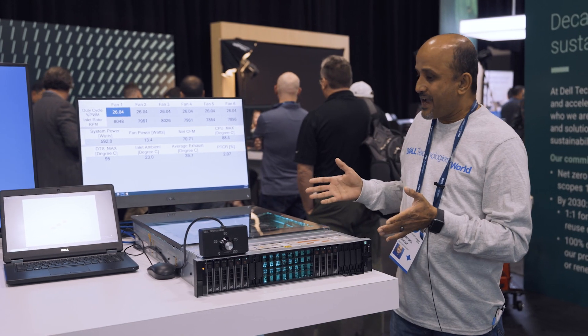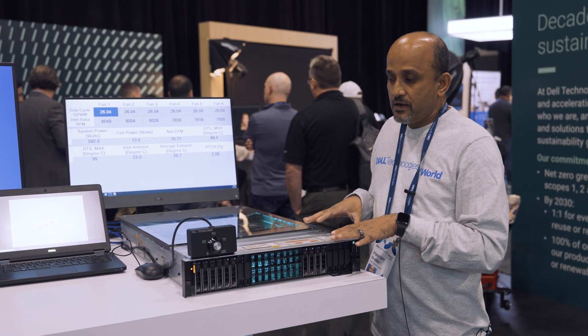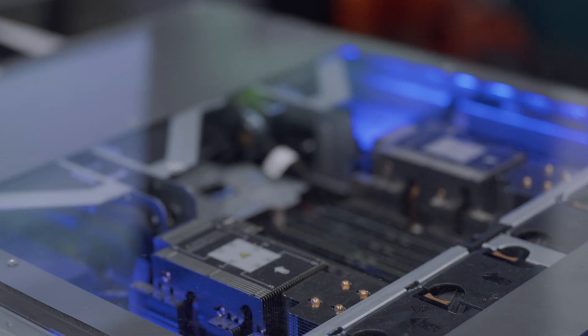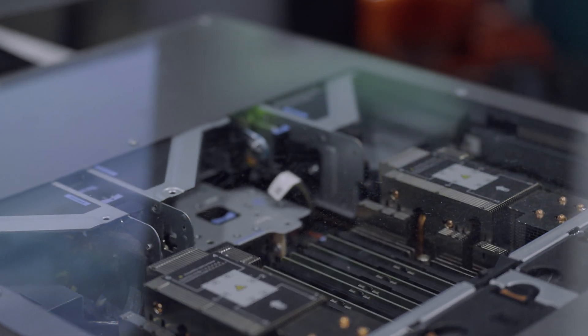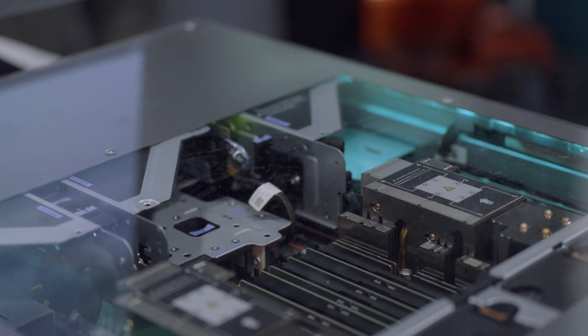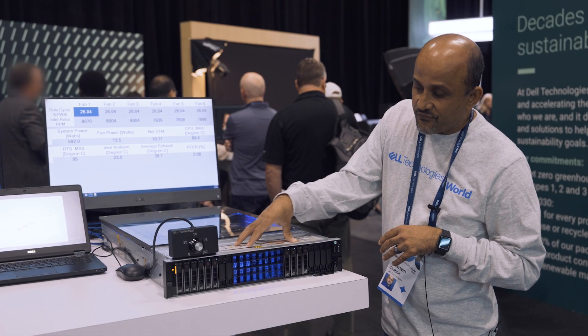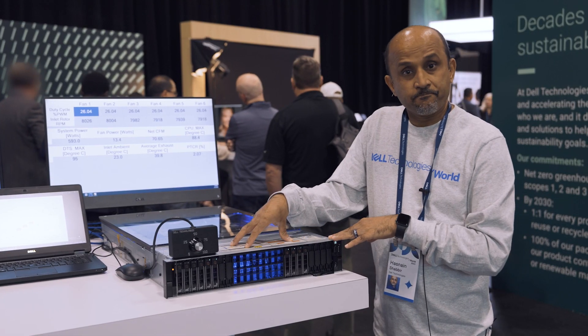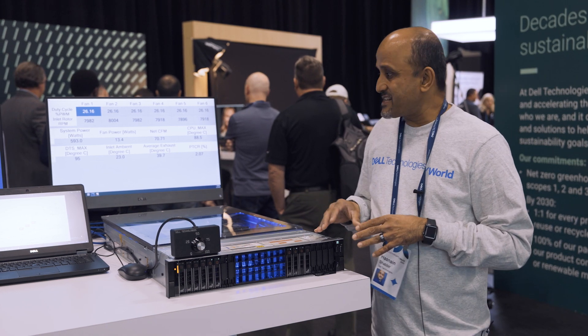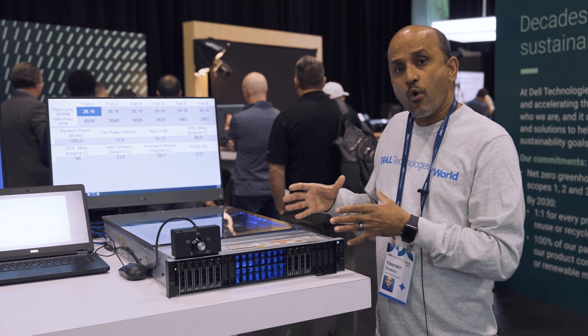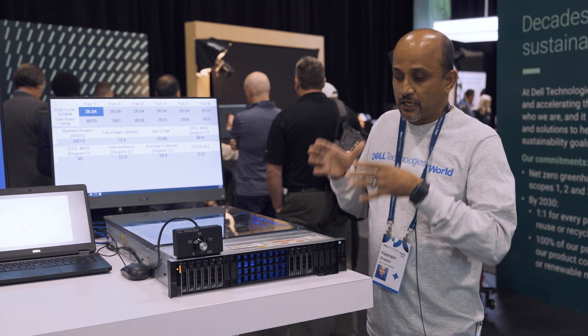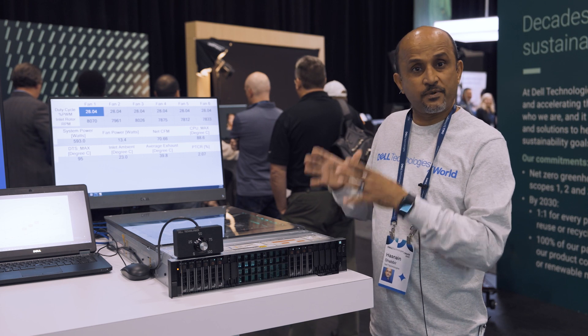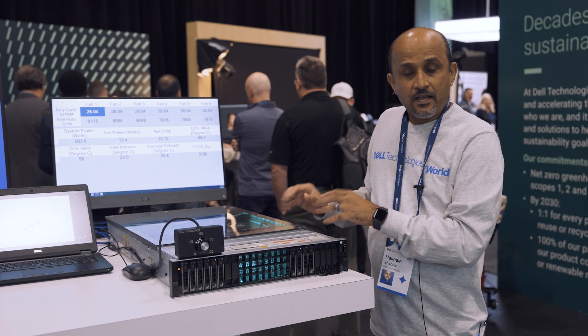This system, for example, is one of our 2U boxes in which the front end has been optimized for air cooling. The idea is how do I run my fans at the lowest possible speed and cool this box. Fan power is a significant chunk of waste power in the box.